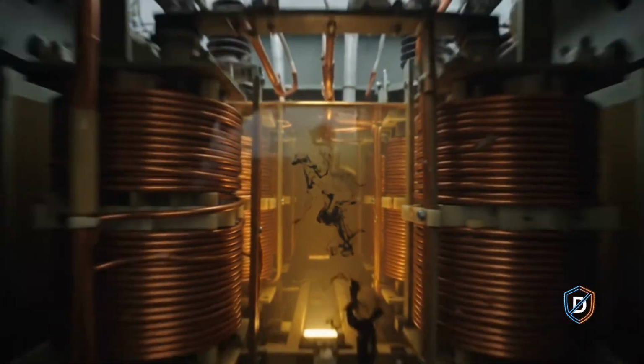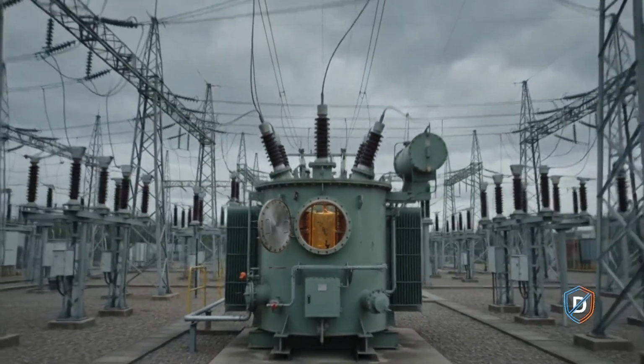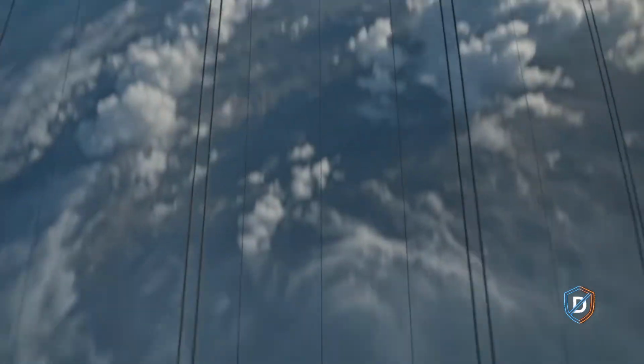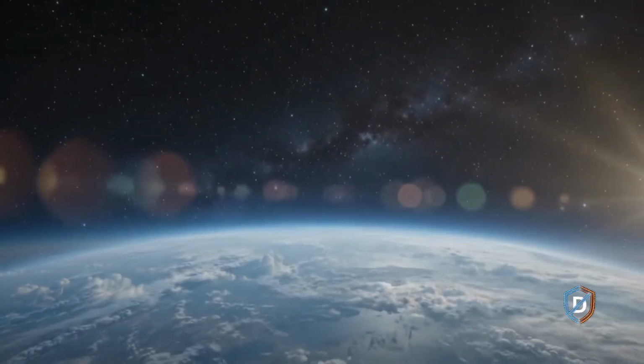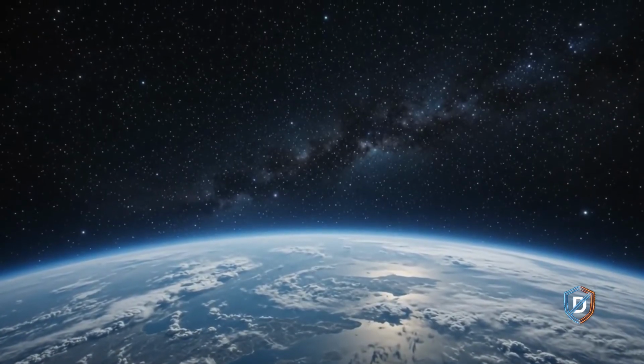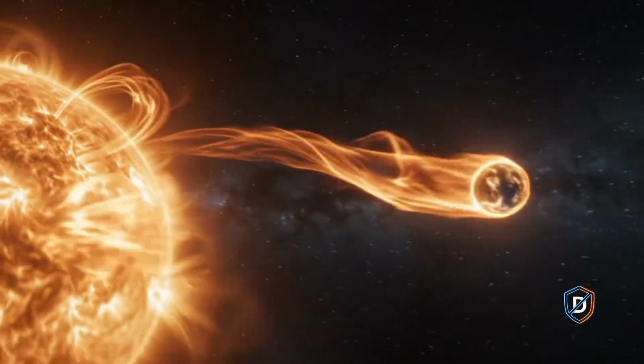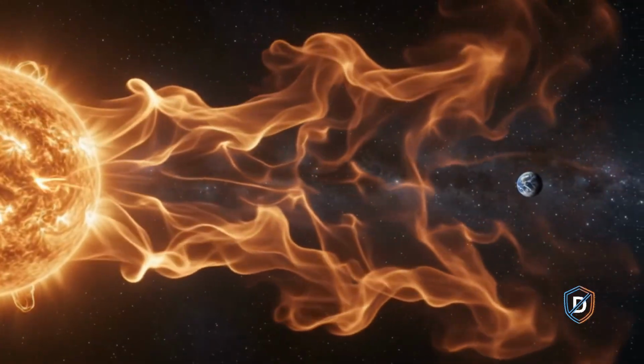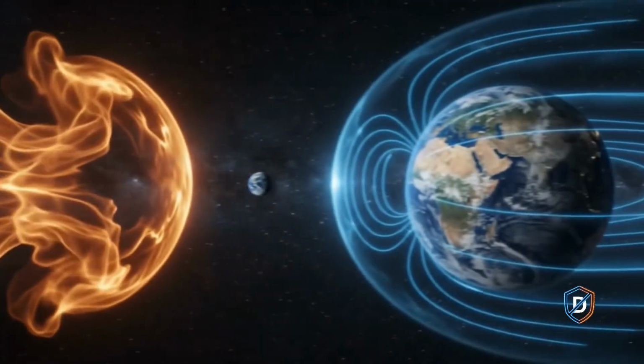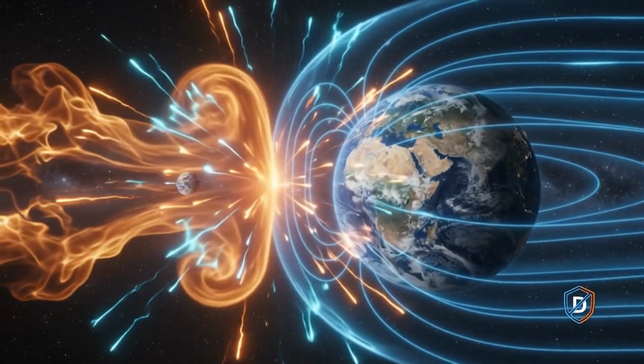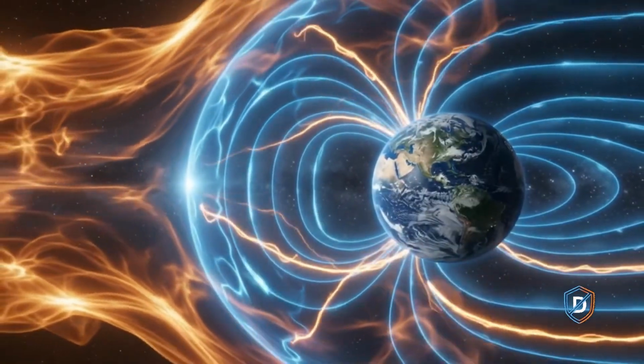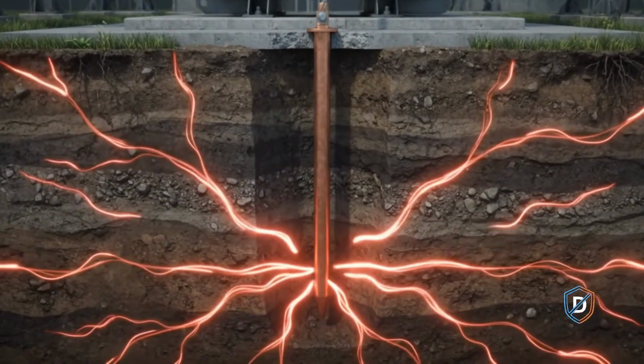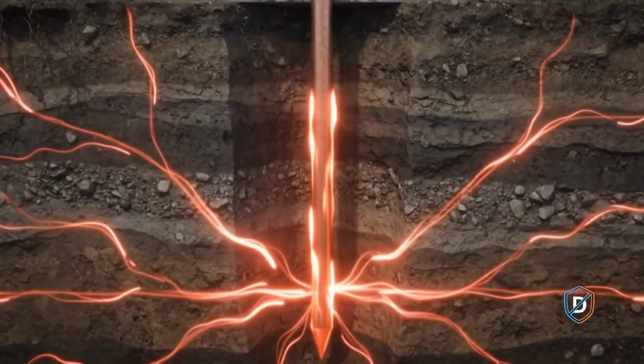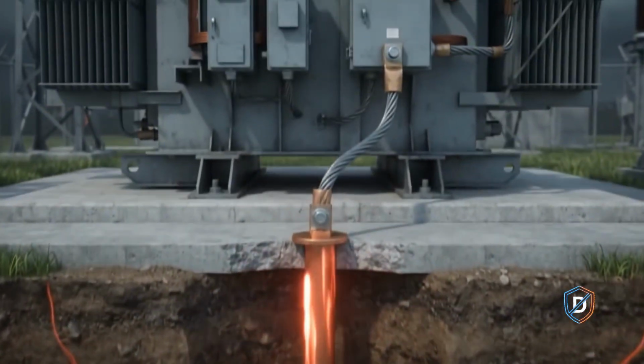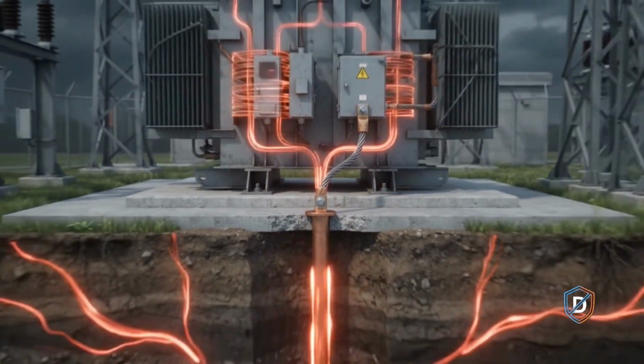While mechanical wear weakens the transformer internally, the real catastrophe requires an external trigger from space. A solar flare hurls billions of tons of magnetized plasma across space, directly toward Earth's magnetosphere. Seeking the path of least resistance, these low-frequency direct currents flow straight up substation ground pins.